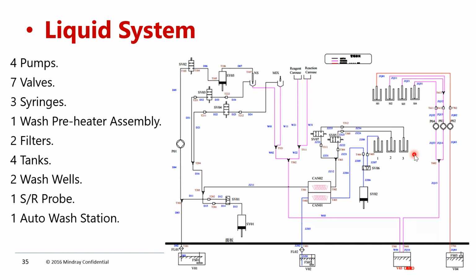There we mentioned that after dispensing the third cycle, there is a wash water. It will go for the reading, and if the reading is within the intensity limits, it will be okay. If it is below the limit, it will trigger the alarm, right? So after the third cycle dispensing the water, it will drain, then it will go to the drain probe. This probe will aspirate and clean the cuvette. It will remove the water from the cuvette. This probe has a wiper. So it will go down two times and aspirate whatever residue is in the cuvette.